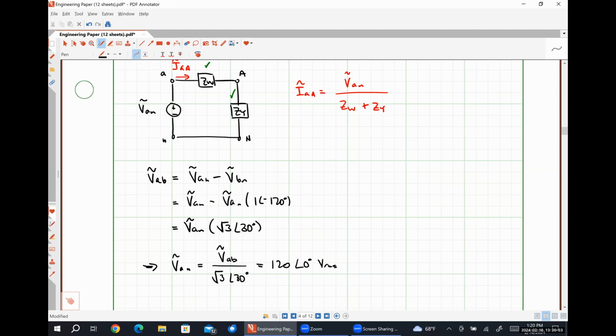Anyway, if you pop open that breaker panel, you'll see that it has a listing on the nameplate that says something like 120/277. Bogart Hall has three-phase power because there are machines in here that require three-phase power. The 120 is the phase to neutral voltage, and the 277 is the line to line voltage. Depending on how you connect things to the internal circuits in this building, you have access to either 120 volts or 277 volts.